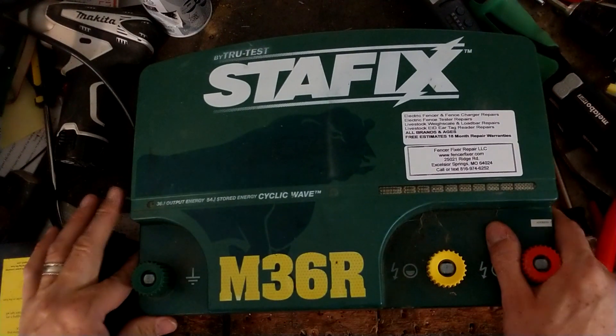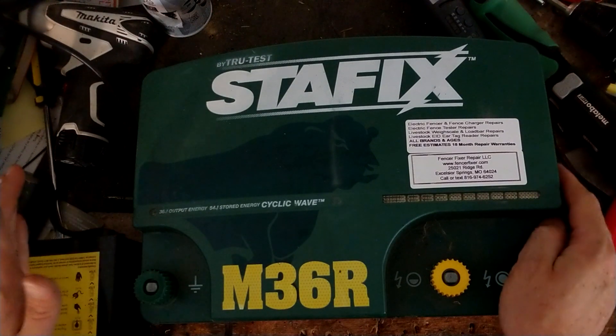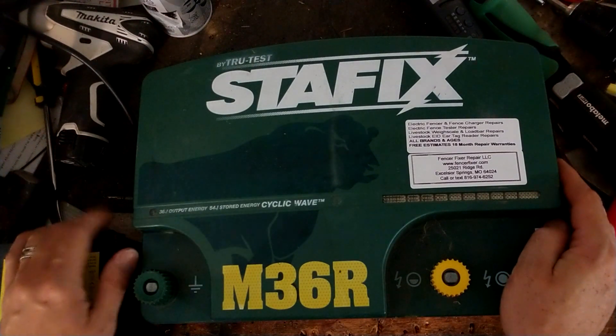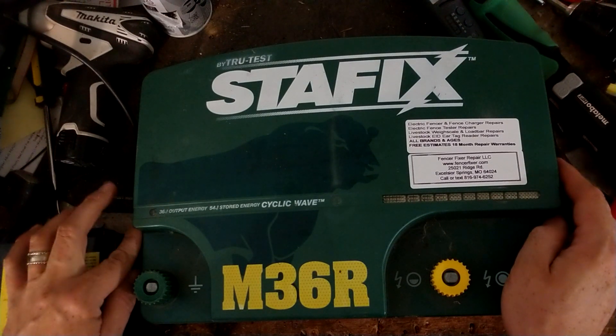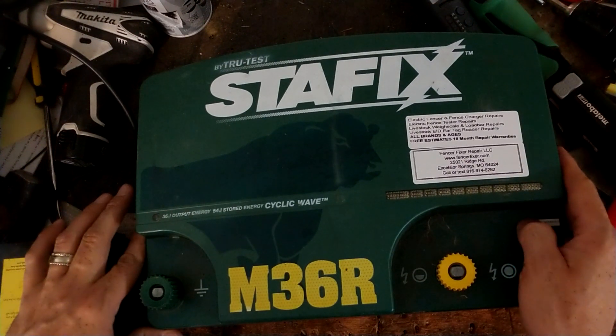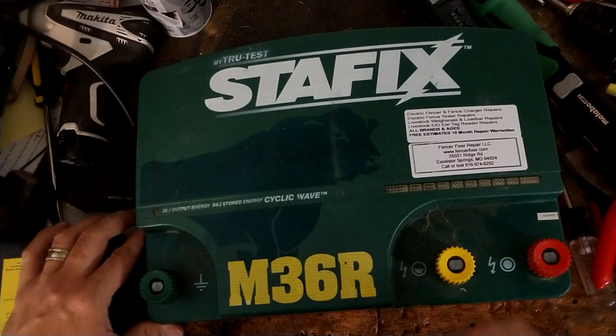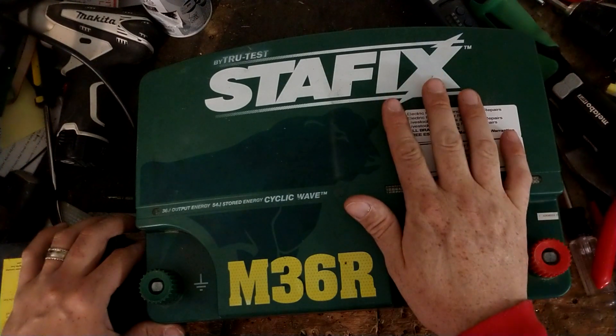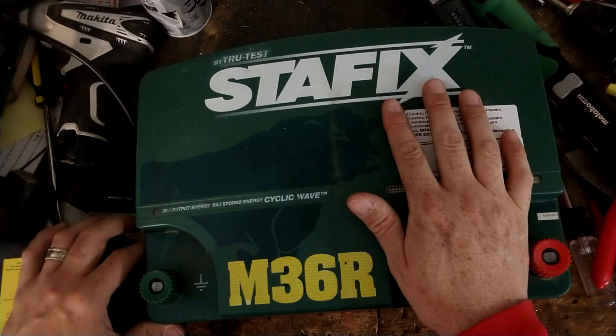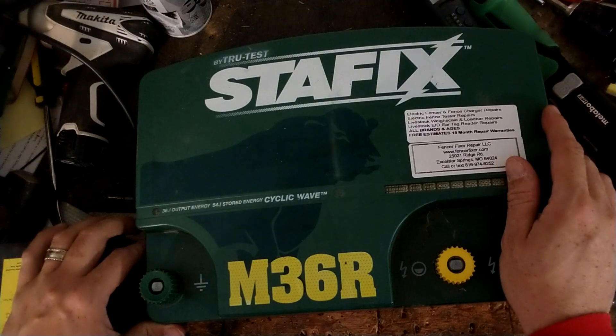It's a pretty slick unit — pretty reliable. Excluding lightning, these things typically run you 10 years or better. I've seen it be a little less than that, but typically you get 10-plus years out of one. I don't remember how old this one was. It had a sticker on the inside, but I didn't pay close attention to it. I just started working on it.